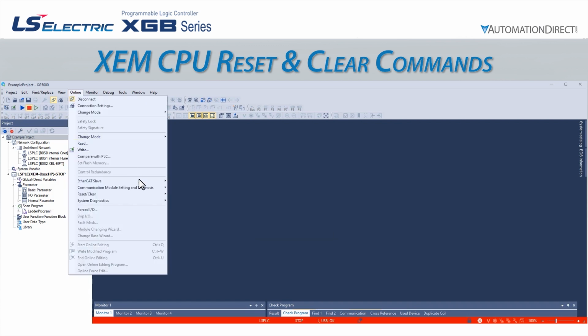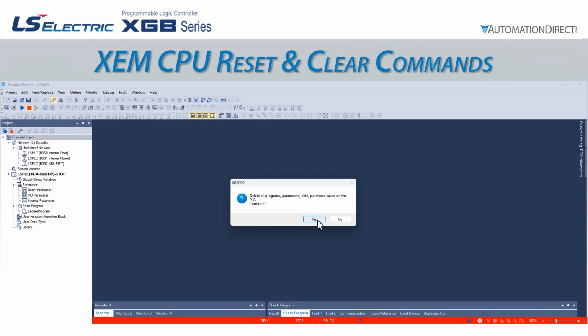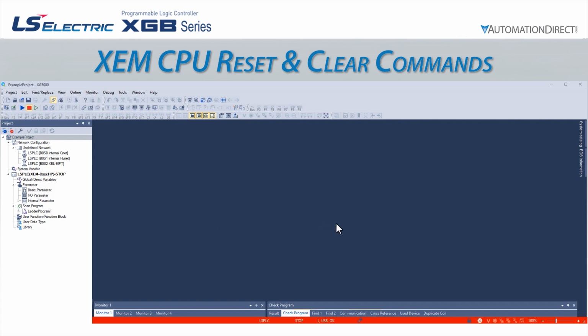Finally, if we select the Clear All PLC command, this may be done online or offline and will delete everything in the PLC, including the IP address. This must be done with the mode switch in the stop position, but the CPU may be in stop or run mode, as the software will force us to put the CPU in stop mode to perform the clear all.